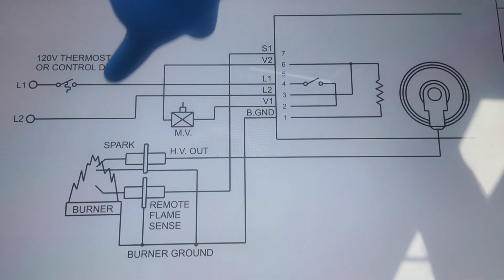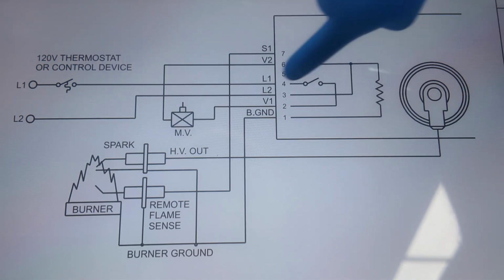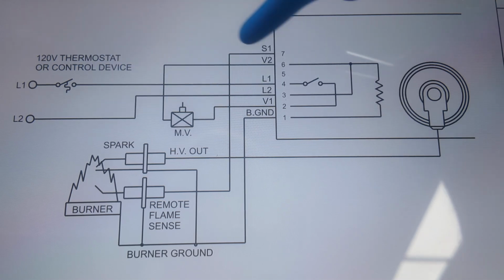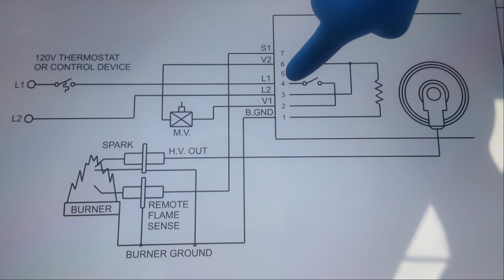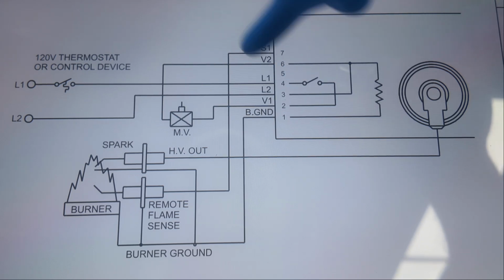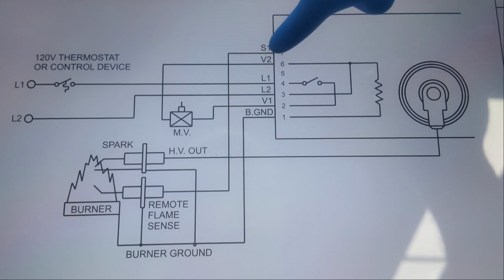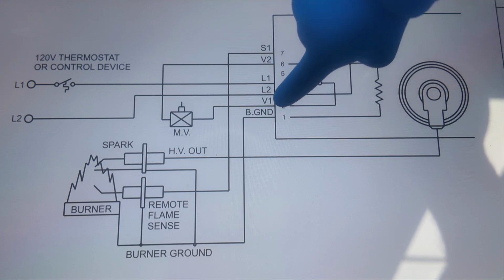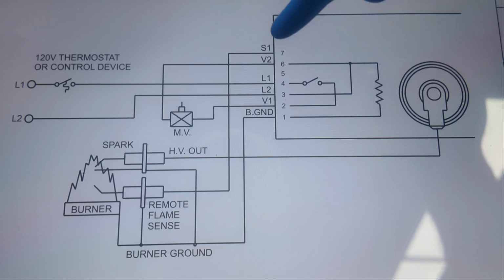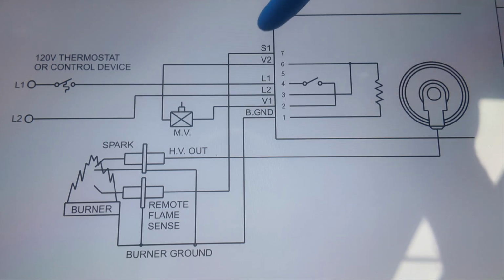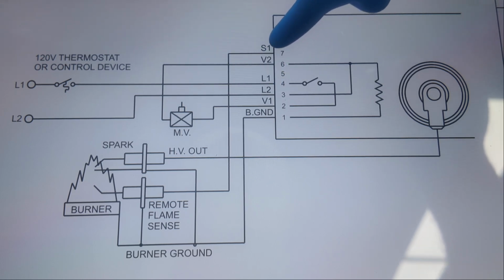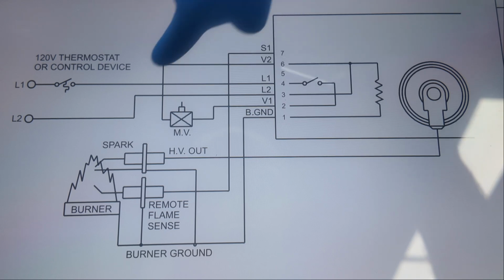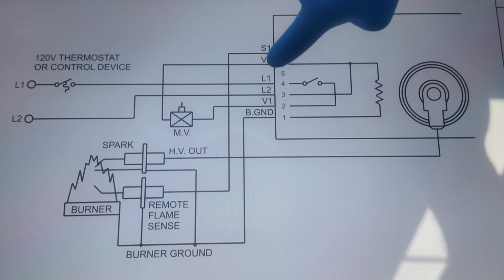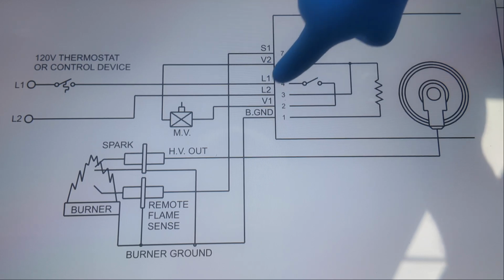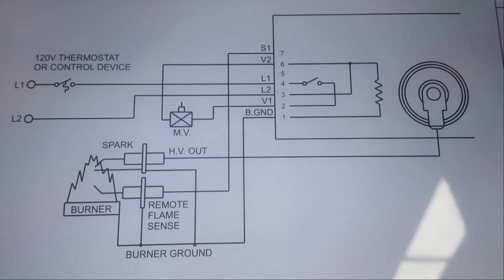If we know our incoming voltage is correct, and we disconnect S1, and we turn the voltage off and back on at L1 and L2, or 120 volts, and we do not get power out V1 and V2, 120 volts AC on V1 and V2, we have a bad board. Because the S1 wire is the only thing that controls this board. Incoming power and S1. Only two things. If S1 is not connected to anything and we put 120 volts to L1 and L2, we should get 120 volts on V1 and V2 after ignition time.